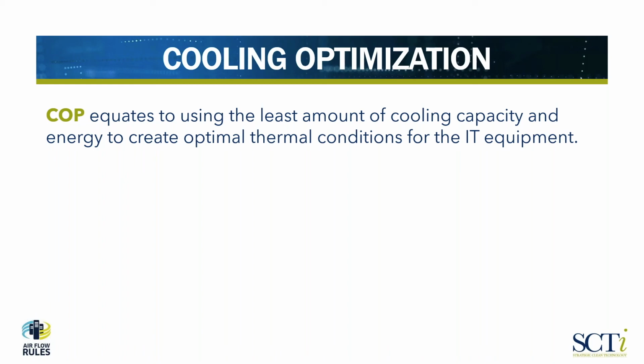First, we optimize airflow, which allows the least amount of cooling capacity to be used to meet the needs of the IT equipment. By reducing operating cooling capacity, we reduce cooling energy costs, and usually our results are a very substantial reduction in cooling costs. The primary objective is to ensure the IT equipment operates in an optimal thermal environment while operating costs are reduced.